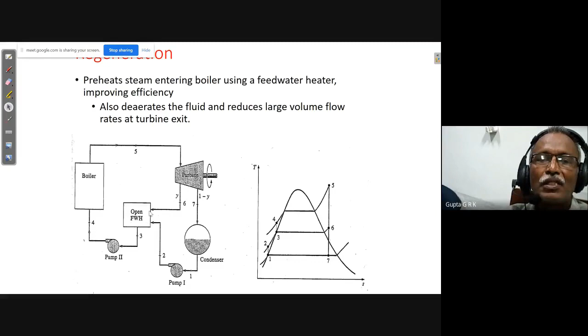And combining all together, we lower the condenser pressure. Limitations I am telling here: how much can I reduce the condenser temperature and pressure? There must be at least a 10 degrees centigrade difference between the condensing water and the condensate water. Okay, so I have to have at least 10 degrees centigrade. And the quality at the exit of the turbine should be at least 88% dryness. It cannot be more than 12% wetness. This is the limitation for lower condenser pressure.